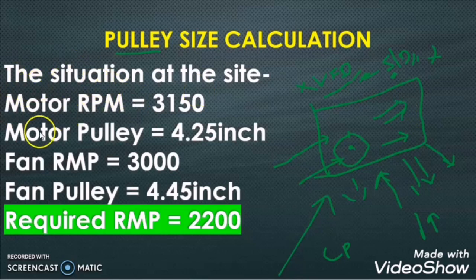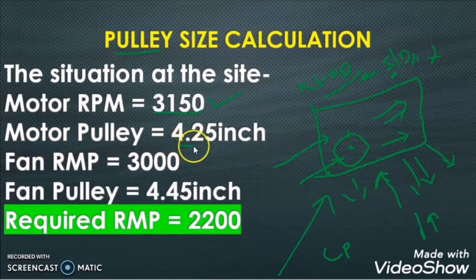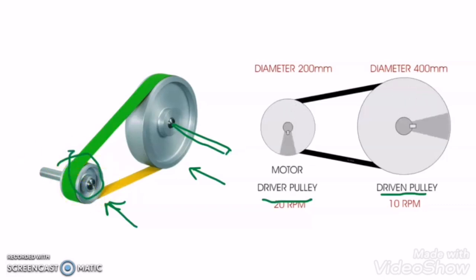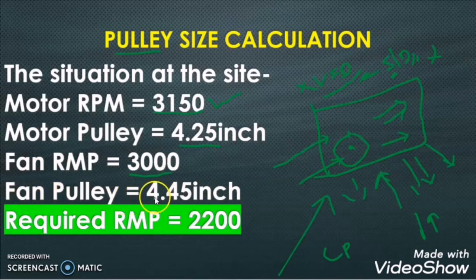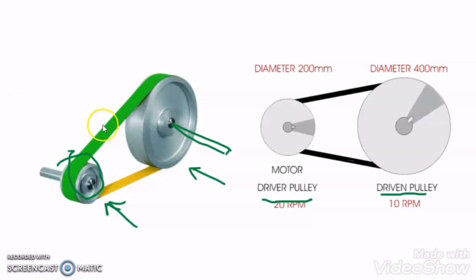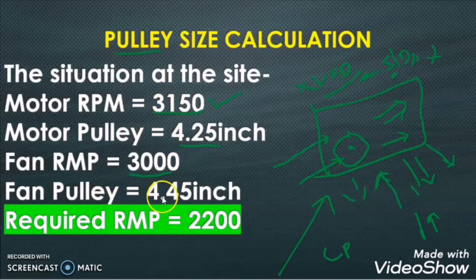In our site situation: the motor RPM is 3150, the motor pulley size is 4.25 inches. The fan RPM was 3000 RPM, and the pulley connected with the fan was 4.45 inches. In this condition, the fan RPM is 3000, and due to this high RPM the water is being carried out by the air, causing water to drip from every corner of the FAHU. We need to reduce the fan RPM.